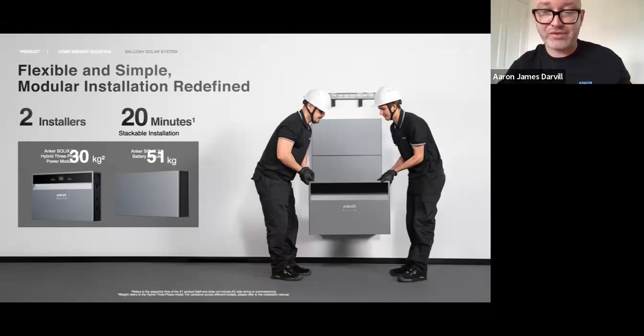Like I said, we do a wall bracketed version, which you can see the guys in this picture are currently installing. Based on a single phase inverter power module, it's 19 kg and the 3-phase is 30 kg in weight. The individual battery modules of 5 kilowatt hours are 51 kg per individual pack. We do advise it is a 2-person lift. There are very easy access hand grasps to the side of each of our individual systems, both inverter and battery.